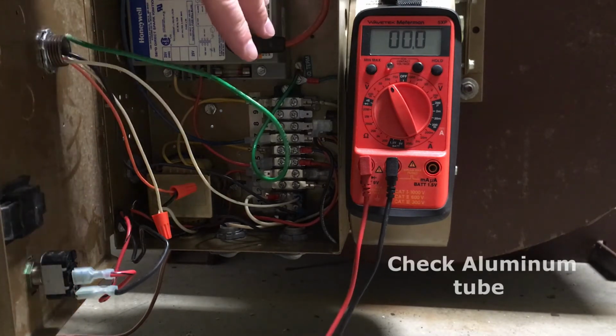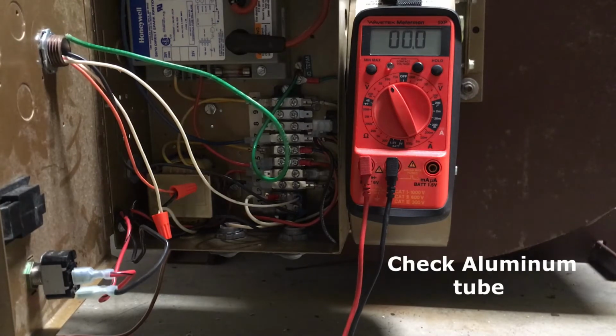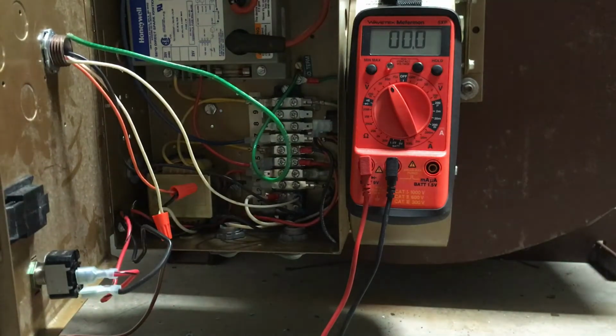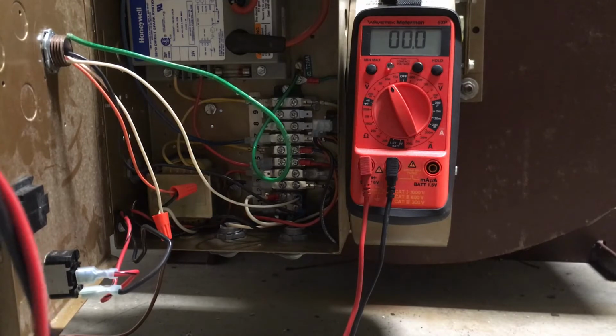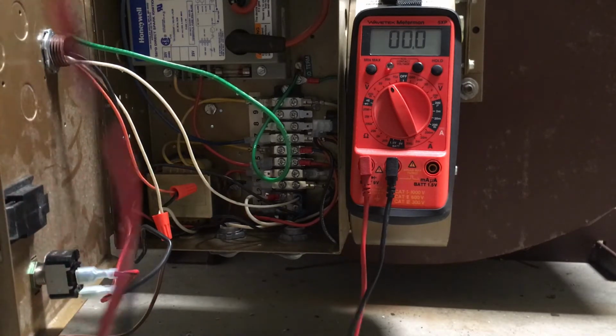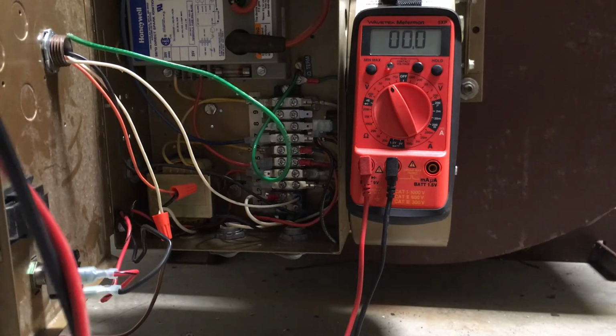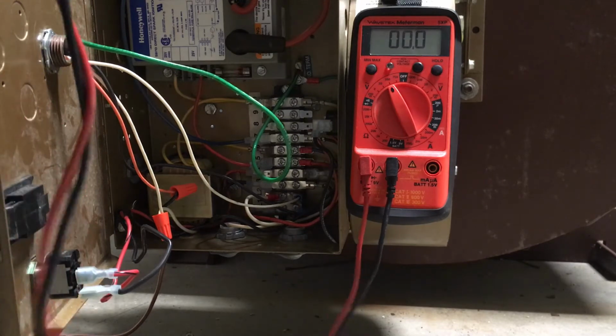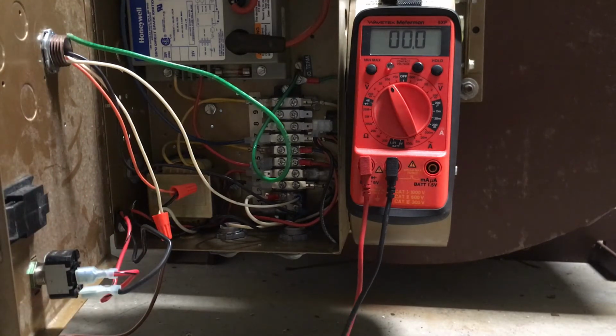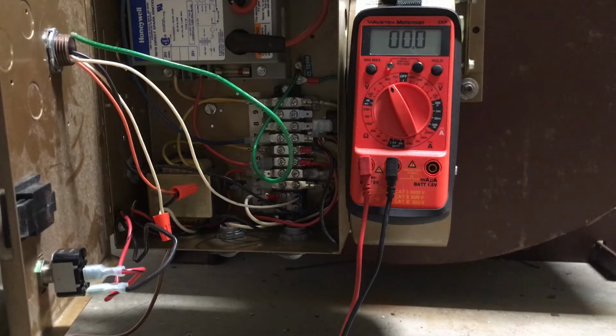So if you're getting 0 voltage there, you want to check that aluminum tube that's going to that switch and make sure that there's nothing plugged up in it, any spider webs, any bugs or water in it or anything like that. That'll prevent the air from going and triggering that switch. So you want to clean that out and verify everything's operating properly. Maybe the switch has failed, so if you have to replace the switch, you put the new switch in, you start everything back up.